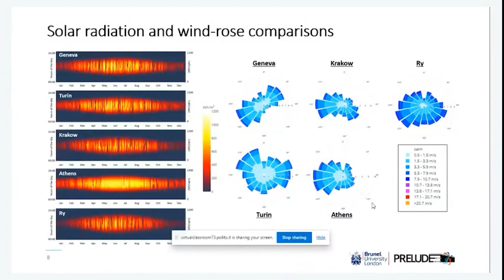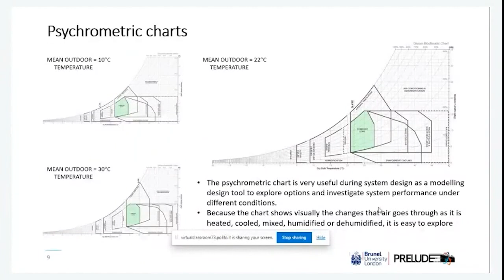The psychrometric chart is very useful during system design as a modeling tool to explore options and investigate system performance under different conditions, because the chart shows visually how the air changes as it goes through being heated, cooled, humidified, or dehumidified. So we need to predict this condition, and the psychrometric study makes it easy to explore changes in the control requirements.